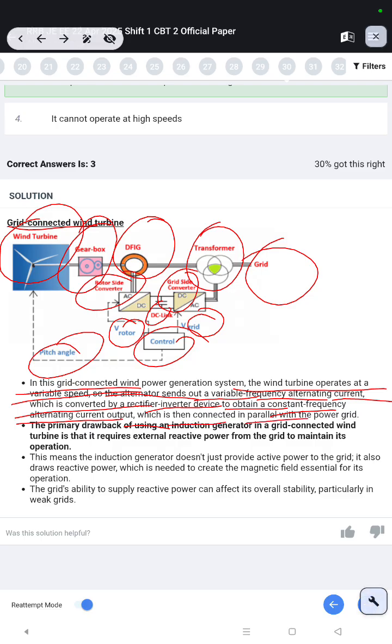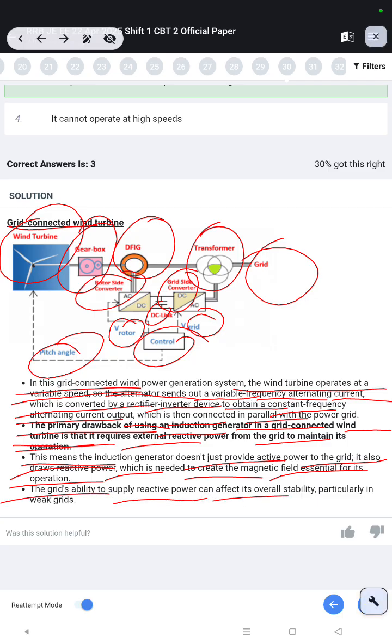The primary drawback of using an induction generator in a grid-connected wind turbine is that it requires external reactive power from the grid to maintain its operation. This means the induction generator doesn't just provide active power to the grid, it also draws reactive power, which is needed to create the magnetic field essential for its operation. The grid's ability to supply reactive power can affect its overall stability, particularly in a weak grid.